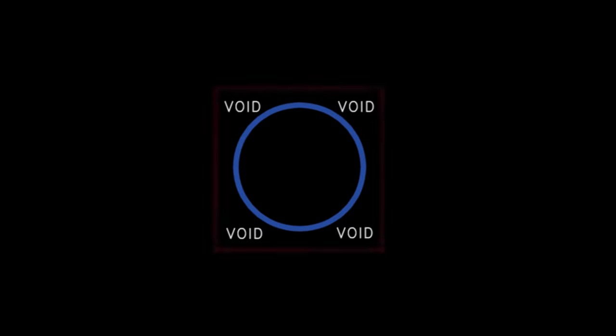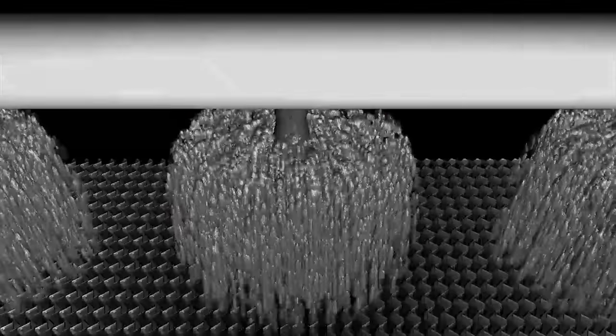Almost all cooling tower nozzles spray in a round or circular pattern, and that's a problem. A circle won't cover a square, unless it's really oversized. So to compensate, companies design in an overlap in the spray pattern to eliminate these voids.